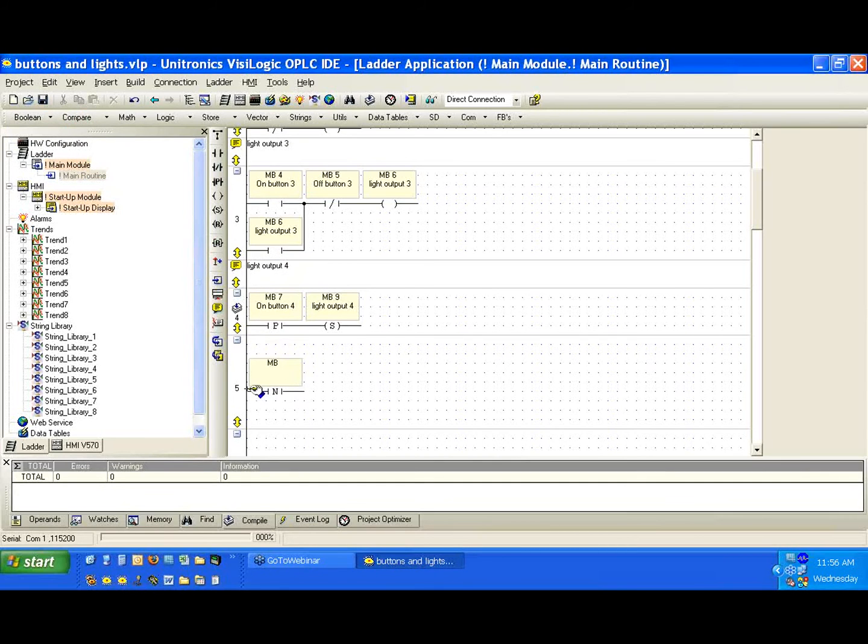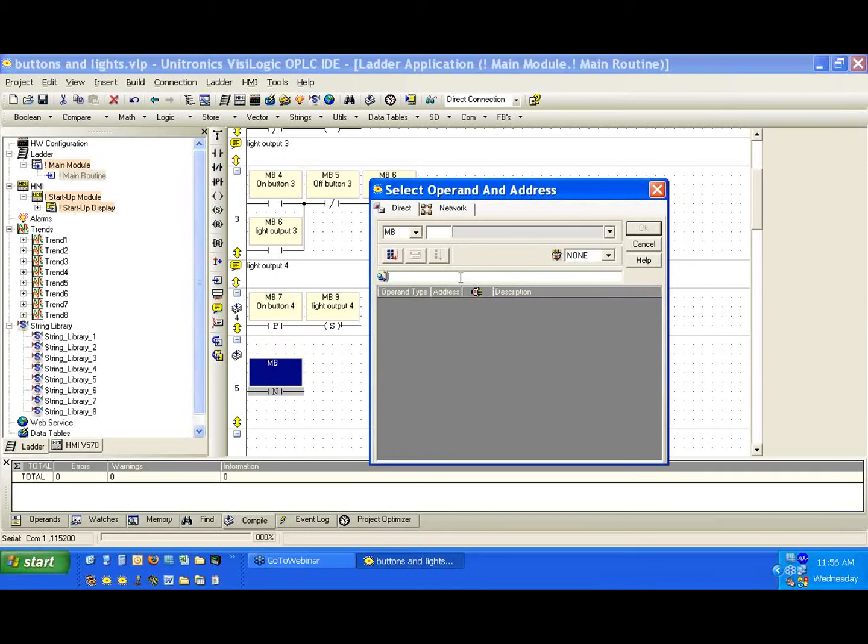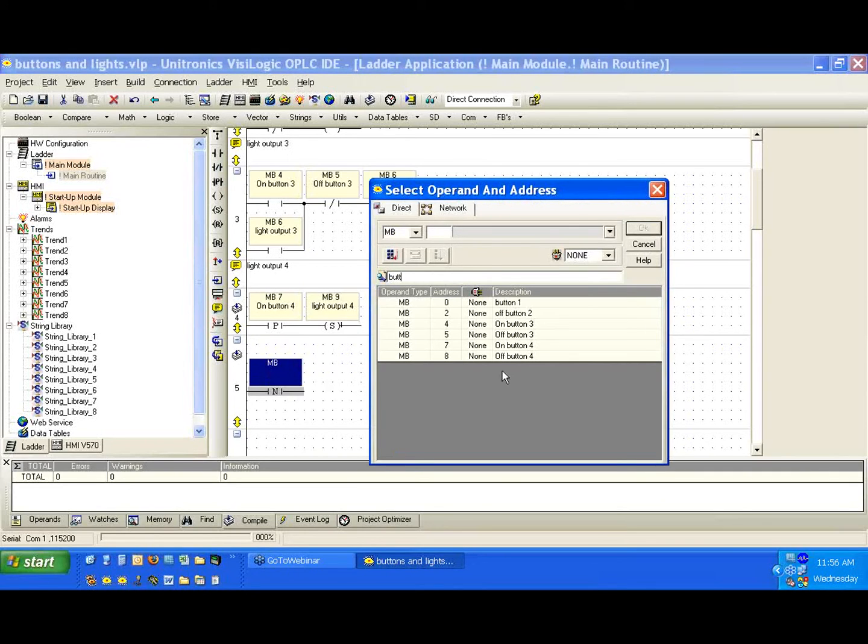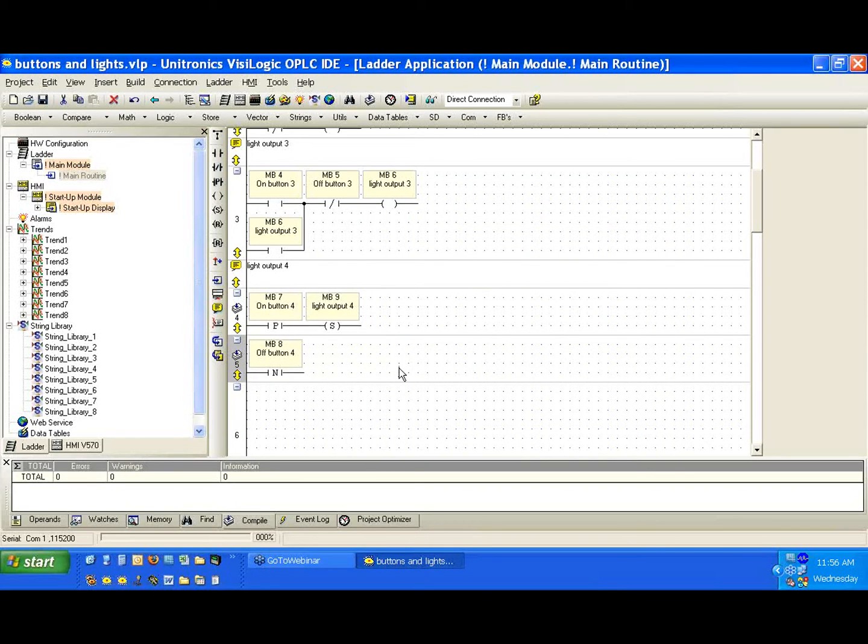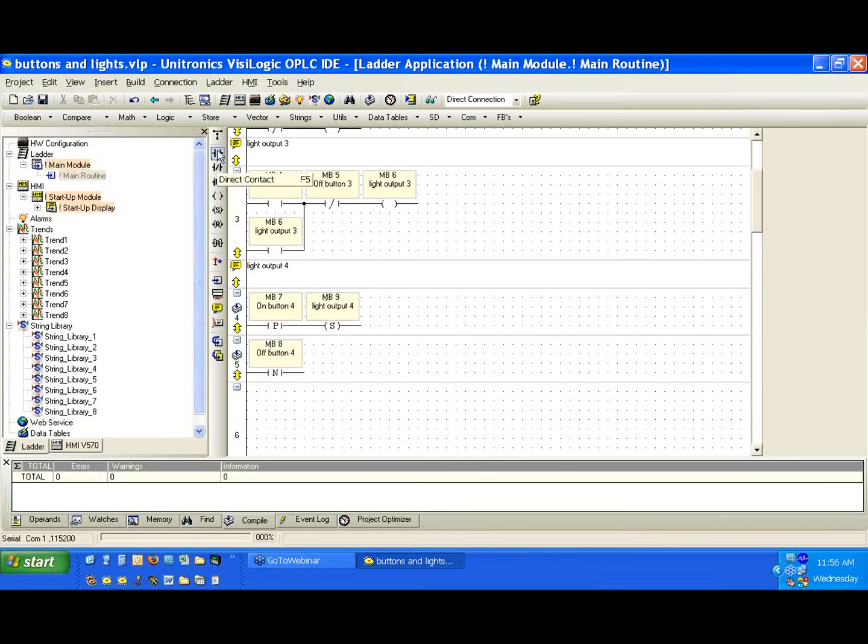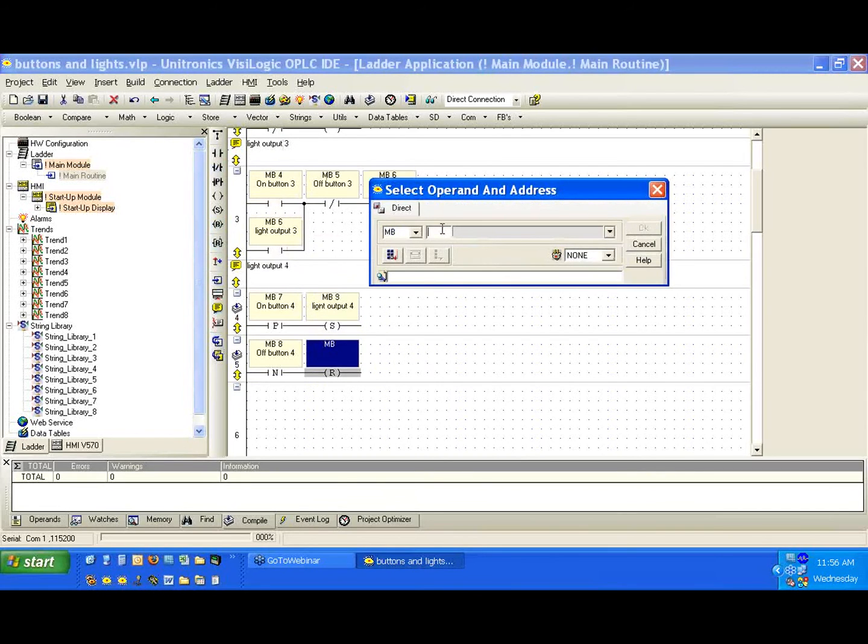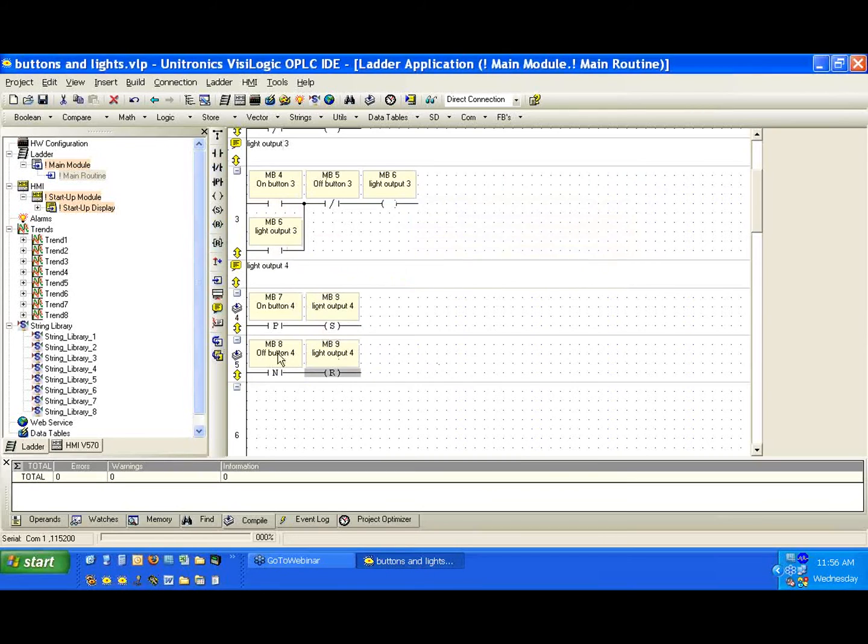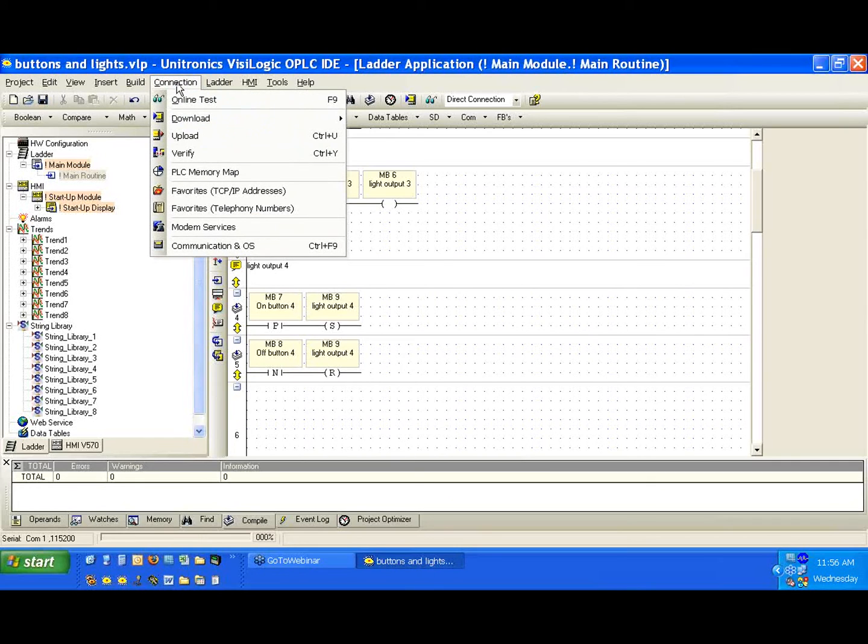What we're going to use is a reset coil. Let's go ahead and take contacts. We're going to do a little interesting experiment here too. We're going to take the negative transition contact for the off button. The negative transition is going to operate similar to the positive transition, but it's only going to output when we let go of the button. So we can hold our finger down on the off button, and only the first moment when we let go will it conduct power through it. Notice that the popular items are also available on this vertical bar. We're going to select the reset coil. When we let go of the off button, we'll reset MB9 and we'll turn the light off.